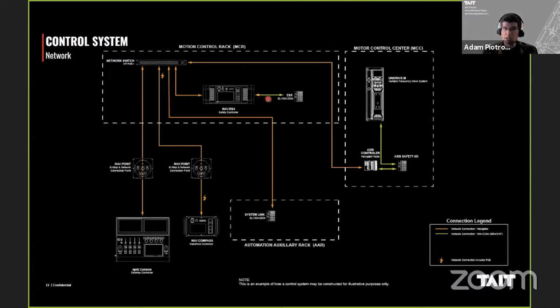We may decide we need to link in some extra IO, so we connect it with that field bus to some IO modules - maybe bringing in extra e-stop inputs, or hold-to-run inputs, a lift system perhaps, to make sure we're getting our clears and things can move confidently, making sure personnel are clear. We also have the ability to link in and distribute the IO outside into different racks or enclosures.